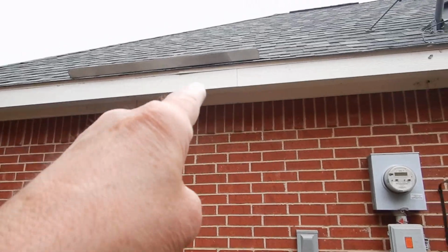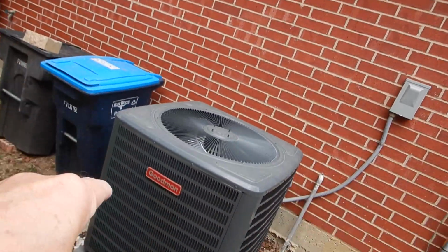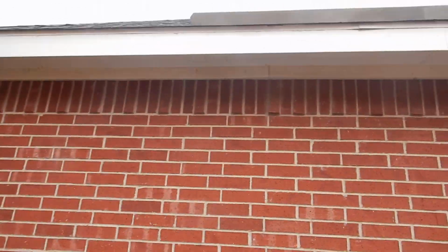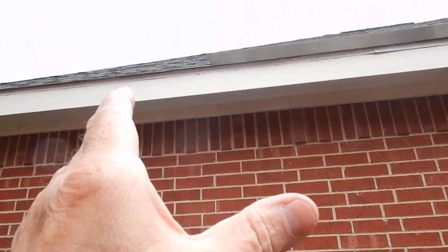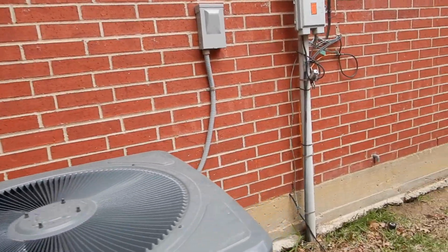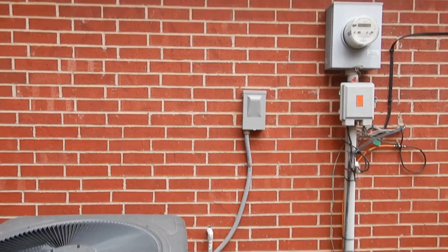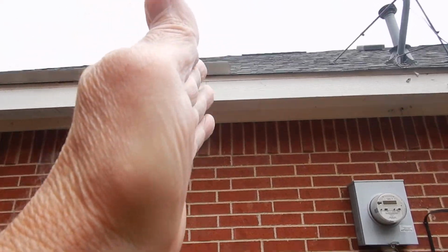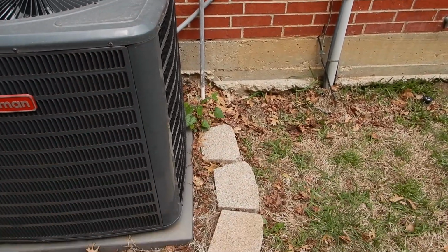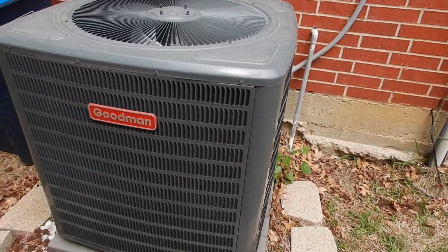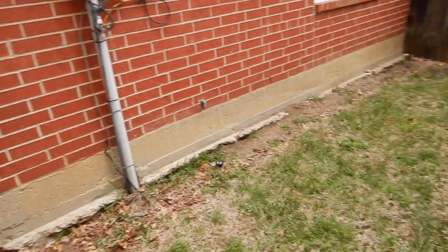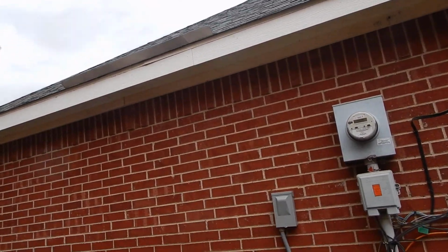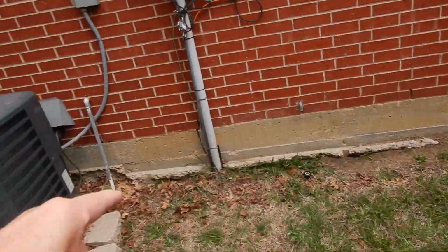There's our rain diverter. It's supposed to go over the unit to keep the water from pouring onto the unit. See, so you come over here, and on this side of the unit, and the diverter comes over here. But when they put the condensing unit in, I'm not saying that the diverter misses it, but it doesn't clear it by even 3 inches probably. So I think the condensing unit could have been better positioned, or the diverter could have been better positioned. I think that probably a rain gutter along this, the house faces west along the south wall, I think a rain gutter is in order, because look at all the erosion that we've got.